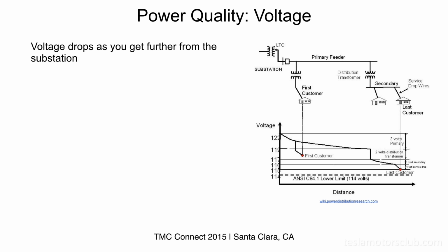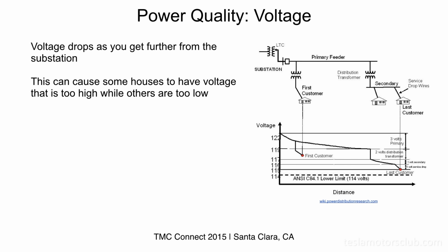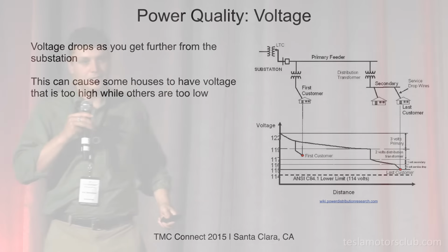Power quality issues - voltage. If you're on a distribution line, we've got this line circuit, and as you go further down, your voltage drops. This can cause problems as they try to regulate it - sometimes houses really close to the substation have voltage that's too high, and some further away are too low. It becomes a problem managing this voltage as the power flows down.